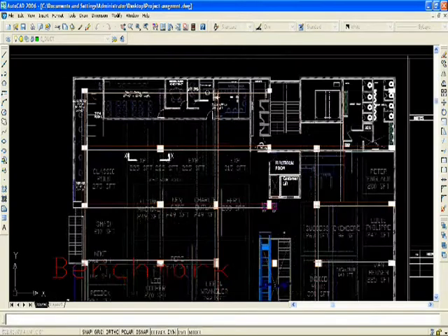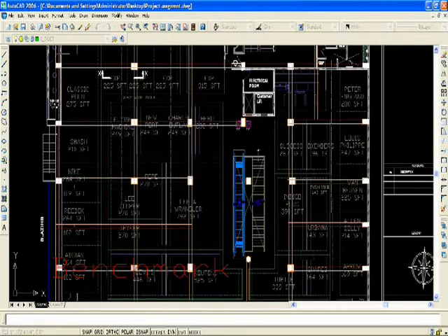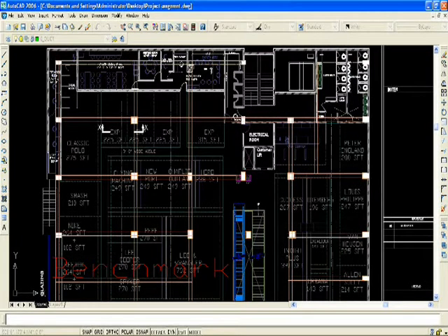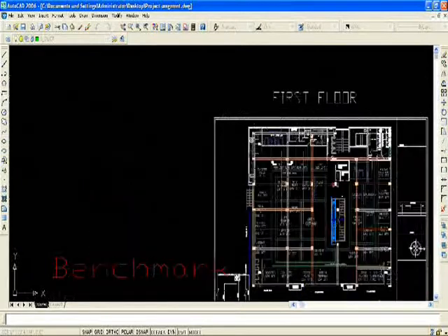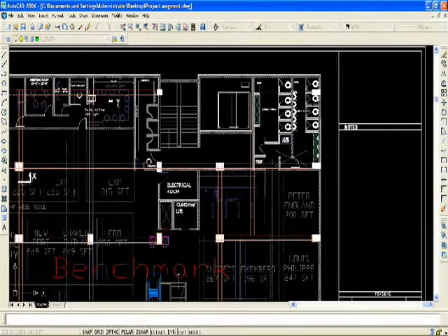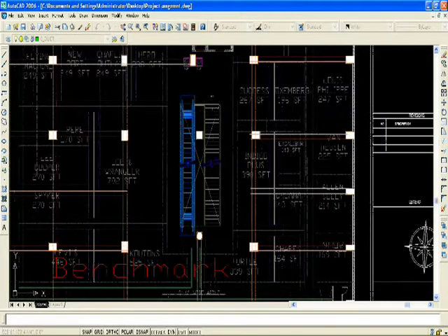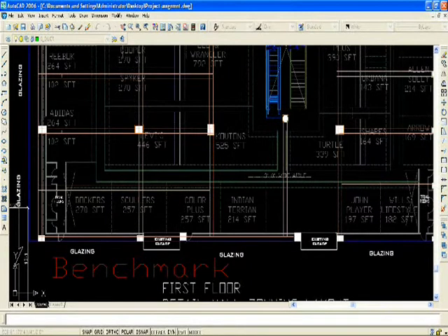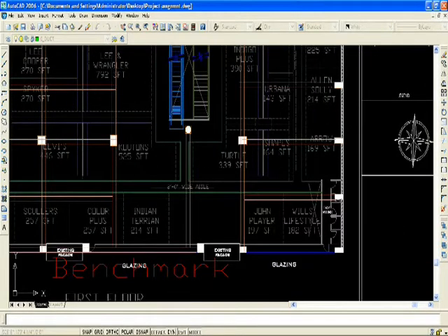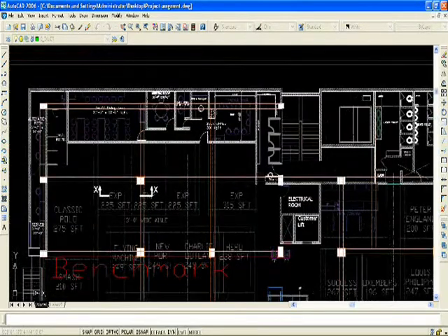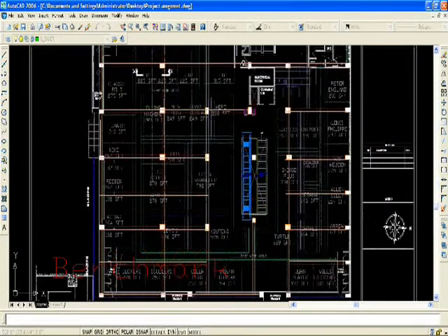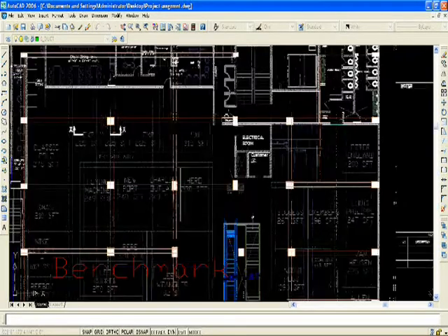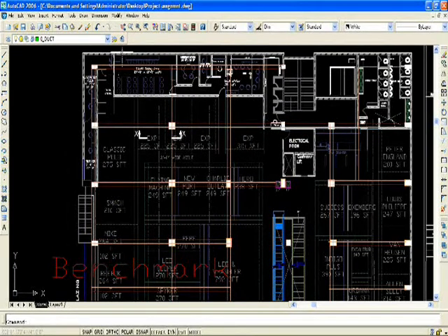We have a total length of around 140 feet and width around 93 feet, excluding the toilet area, which will be ventilated, and those walls can be considered for our partitions. We have to maintain 24 degrees Celsius inside condition with 55 plus or minus RH. Outside conditions, as per weather data, we are considering 35 degrees Celsius with 60% RH at 0.4% cumulative frequency. All walls are 9 inch brick, uninsulated. Glasses are considered non heat absorbent, non shaded, and 7 feet height. Above and below floors are air conditioned, so there will not be a load and it will be considered as zero.